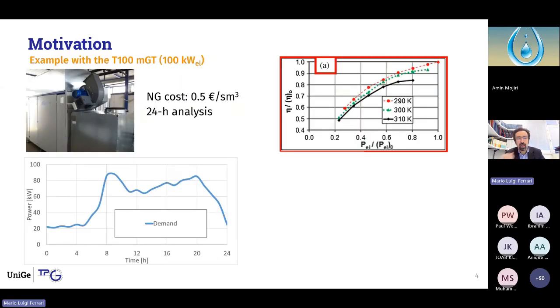So, just to focus the attention on the importance of the optimization of these systems is shown here. It is related to a simple test with a T100 machine that is a microturbine able to produce 100 kilowatt electrical power for a 24-hour analysis. So, considering the demand that is shown below in light blue, it is possible to control this machine to follow the demand with this standard approach. It is named as case 1. However, the efficiency of electrical generation is not constant. It's lower at lower loads. Maybe if the T100 machine nominal efficiency is about 30%, at low load could go down to 15%.